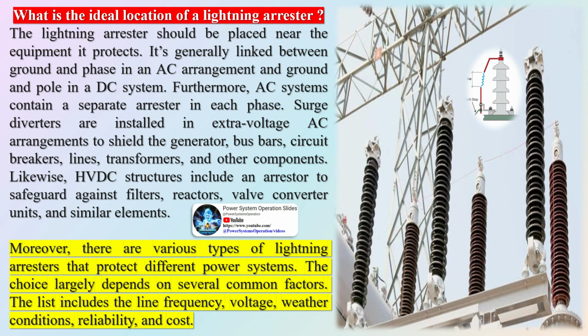These devices are used to defend the power systems by forwarding the high voltage surges in the direction of the ground. And these power systems and overhead lines can also be protected from the direct strikes of lightning by using a ground wire or earthing. The lightning arrestor diagram is shown below.